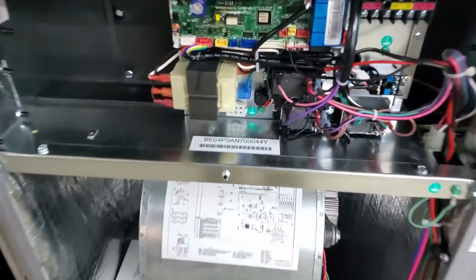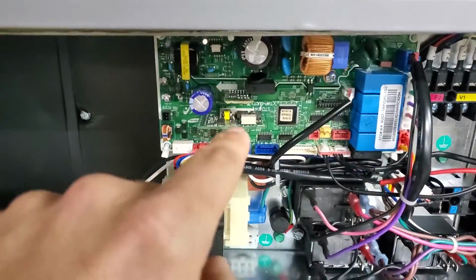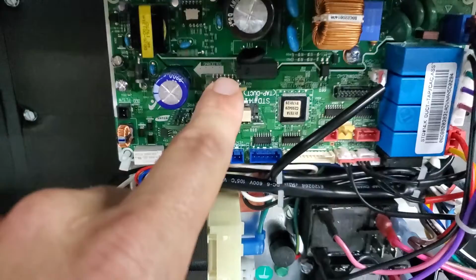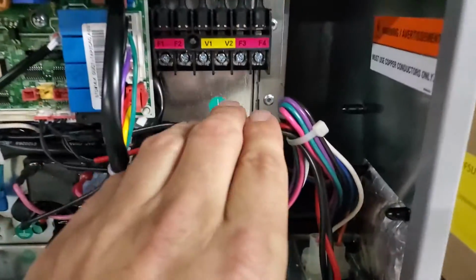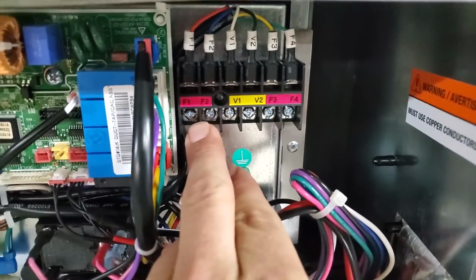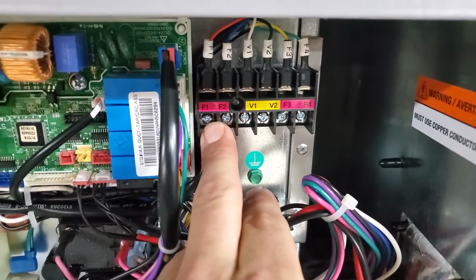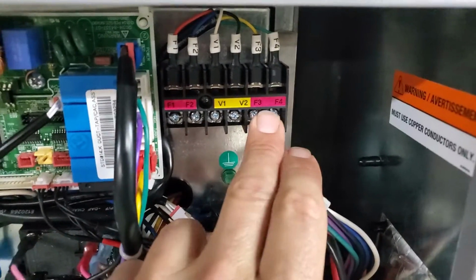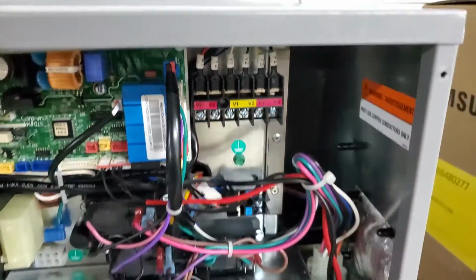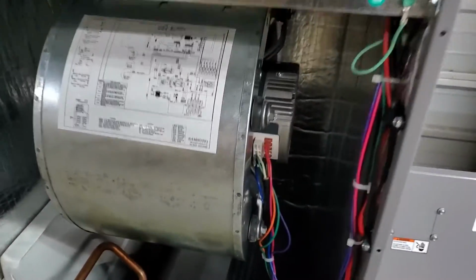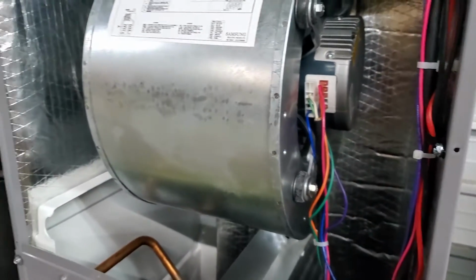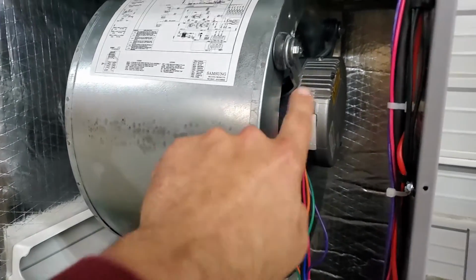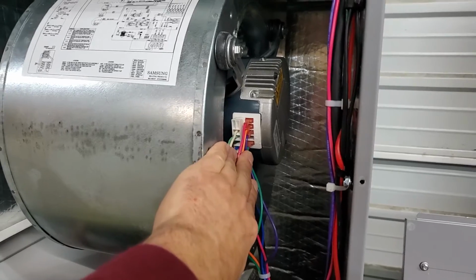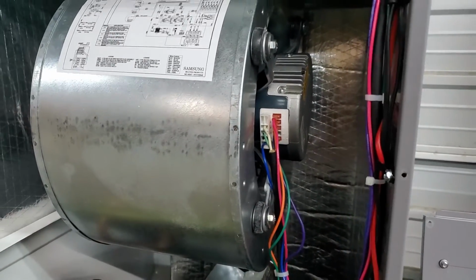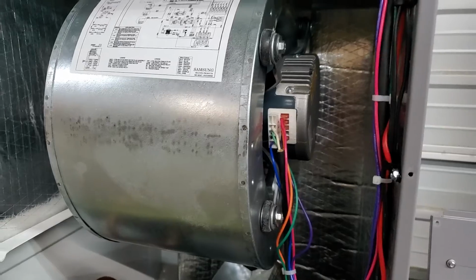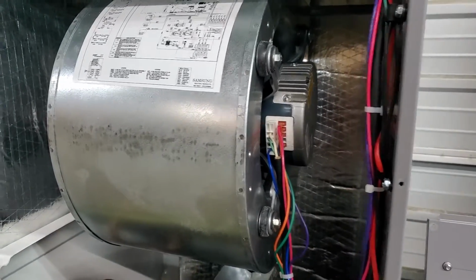And let's talk about the indoor unit now. The indoor unit has its main PCB, PBA, and we have a removable EEPROM here. We also have our terminal block where we have our F1 and F2 communication from the indoor and outdoor unit. F3 and F4 communication to our wired controller, our thermostat. Now we have a high efficiency, constant torque motor. This indoor motor has adjustable taps for the speed, 1 through 5, low to high, so we can get the airflow that we need just by changing a speed tap to match the static.